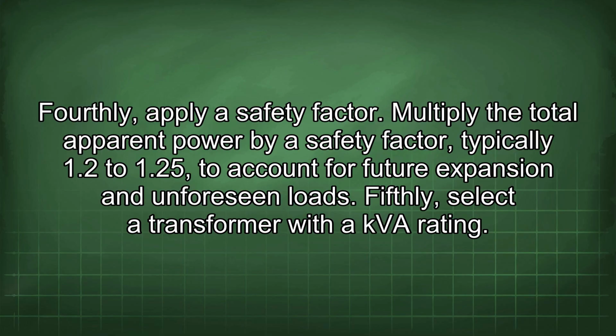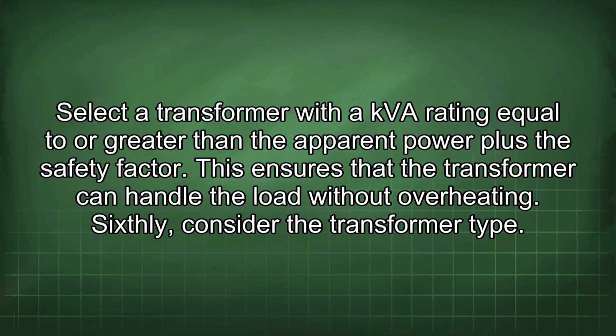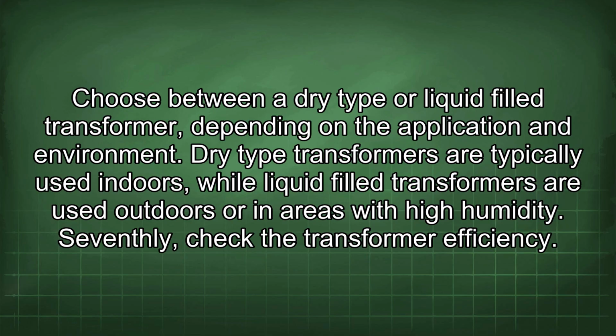Fifthly, select a transformer with a kVA rating. Select a transformer with a kVA rating equal to or greater than the apparent power plus the safety factor. This ensures that the transformer can handle the load without overheating. Sixthly, consider the transformer type. Choose between a dry type or liquid-filled transformer, depending on the application and environment. Dry-type transformers are typically used indoors, while liquid-filled transformers are used outdoors or in areas with high humidity.